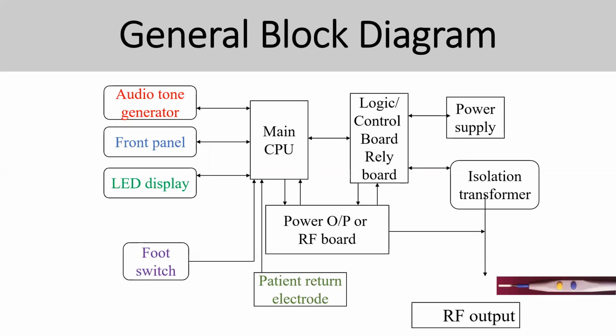General block diagram: when you talk about the block diagram, I always break it up into audio generator, front panel, LED, foot switch, main control CPU unit, logic control board, relay, power operation or RF board, patient return electrode, power supply, isolation transformer, and RF output.